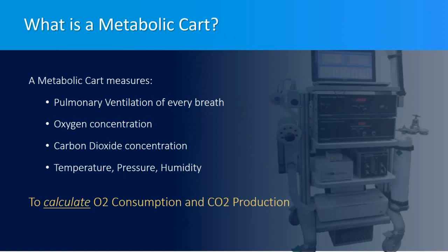A metabolic cart measures pulmonary ventilation of every breath, oxygen concentration (both inspiratory and expiratory), carbon dioxide concentration (both inspiratory and expiratory), and ambient temperature, pressure, and humidity. Temperature, pressure, and humidity are used to convert the metabolic data from atmospheric conditions to standard temperature, pressure, and dry conditions, or STPD. Finally, this measurement data is used to calculate oxygen consumption, CO2 production, and other metabolic data.